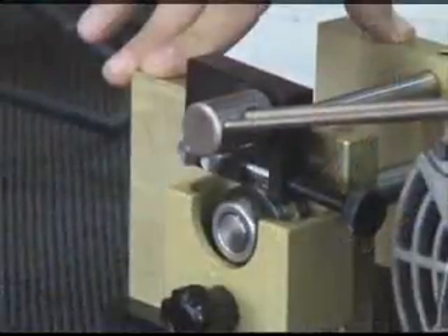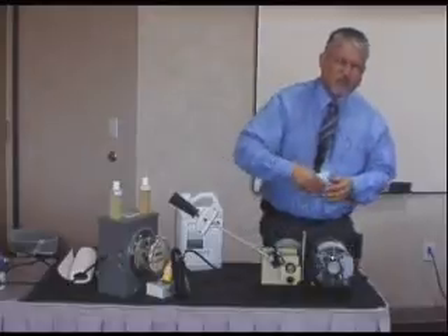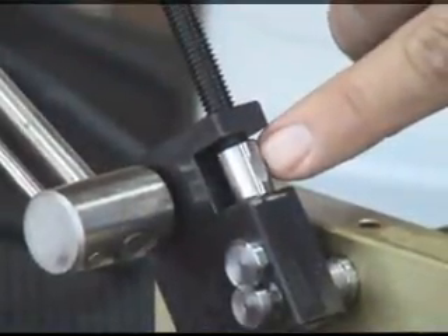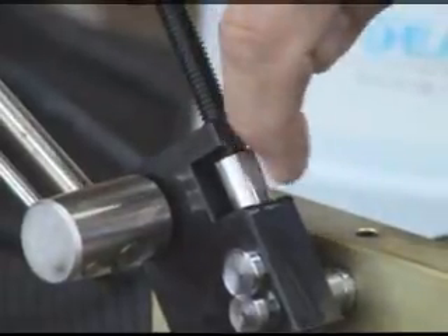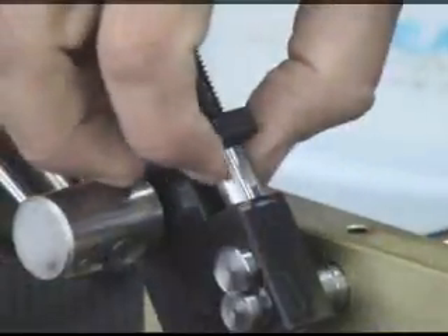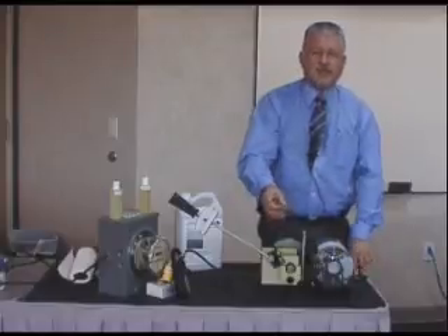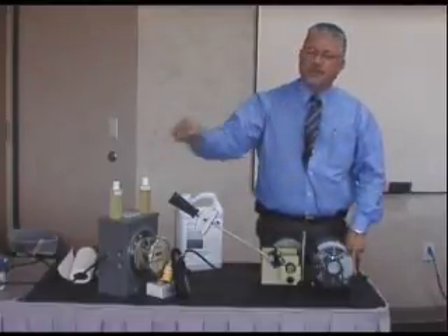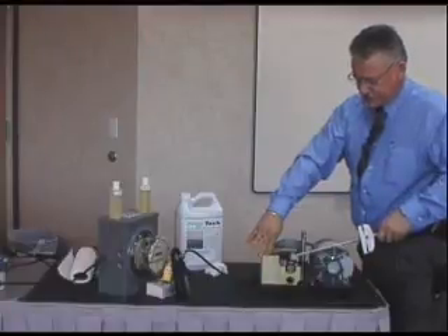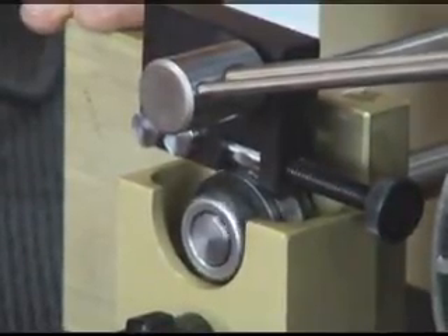Taking a look at this bearing — this is the industrial oil supplied and recommended by the manufacturer for this air conditioning unit. If you look closely, you can see we took a big gouge out of that bearing; it's not smooth, it's quite hot, and it's quite rough. I'm going to use this as my base to compare against. I'm going to turn this bearing 90 degrees so I have another clean surface, then make another gouge about the same size to simulate used equipment, and then add Frigitec to see what difference it makes.